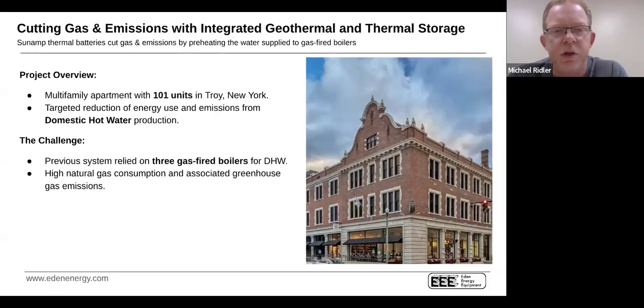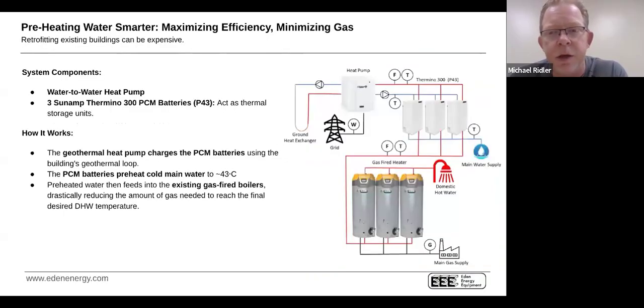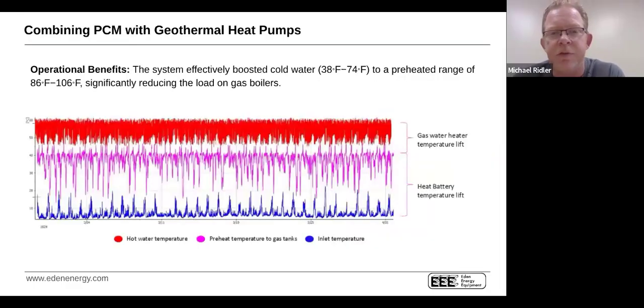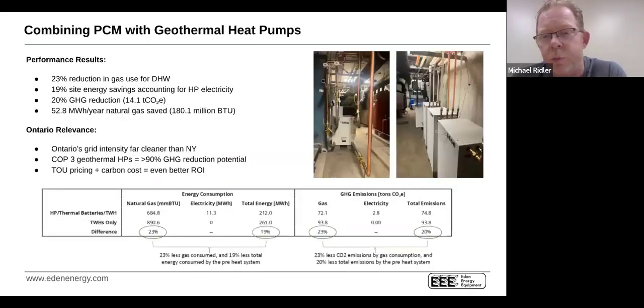This one is particularly cool to me. This is a 101 unit project in Troy, New York, where they wanted to retrofit the domestic hot water to take advantage of a heat pump. As you would all know, this can get complicated because 101 units is a lot. What they ended up doing was using a single 4-ton WaterFurnace heat pump tied to 3 Thermino P43s as preheat for the gas. They were able to reduce the gas consumption by 23% because instead of the water coming in at 38 to 74 degrees, depending on the time of year, it's now coming in at 86 to 106 degrees because we're preheating using the GEO, which results in a 23% reduction in their gas usage, and obviously all the greenhouse gas reductions that come with it.